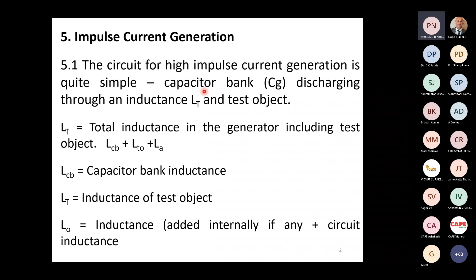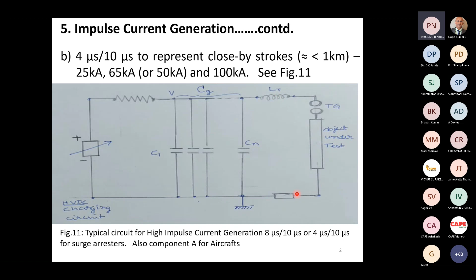Now, impulse current generation is much simpler. What we do is we charge a number of capacitors in parallel and then discharge them through an inductance and the test object. Now, the time to front and tail are decided by the object that we are testing. So this discharges through inductance and the test object. So the wave shape of the current is determined by the value of this capacitance and this inductance, and the test object also. This is a measuring resistance.